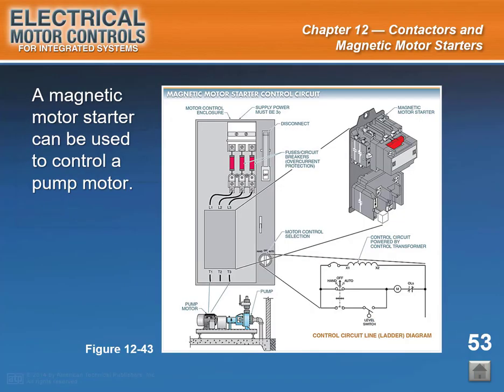Start of slide 53. Slide caption: a magnetic motor starter can be used to control a pump motor. See figure 12-43. When using a magnetic motor starter to control a motor, the starter is wired following a standard line diagram. For example, a pump motor is controlled by a magnetic motor starter that uses a control circuit. The control circuit includes a 3-position selector switch with the 3 positions marked hand, off, and auto, along with a liquid level switch to control the motor starter.